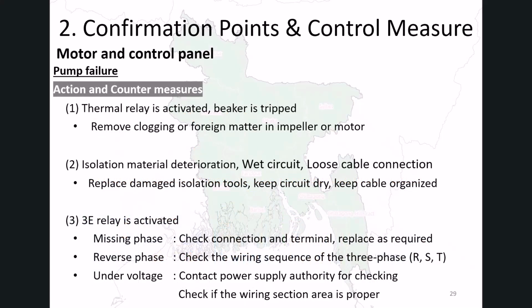The action and countermeasures for pump failure are explained in here. Regarding thermal relay activation or breaker trip. When the thermal relay is activated or the breaker is tripped, remove any clogging or foreign matter in the impeller or motor to eliminate the overload condition.